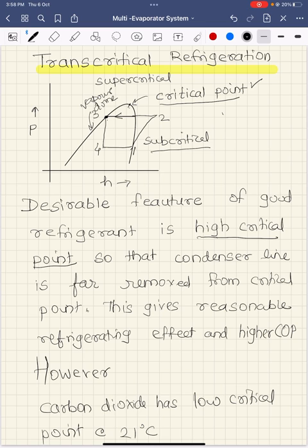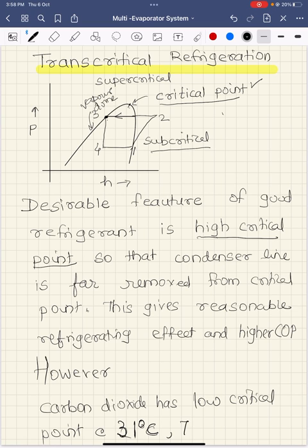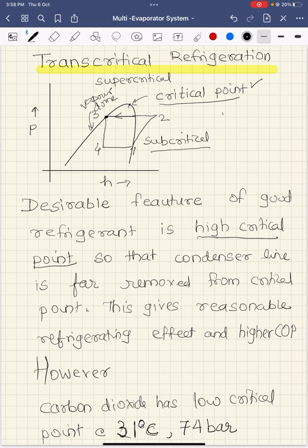What is the transcritical cycle? If you are referring specifically to carbon dioxide, carbon dioxide has a problem in that it is not an ideal refrigerant with respect to the critical point property. The desirable property for a good refrigerant is that the critical point has to be high, but for carbon dioxide the critical point is pretty low — around 31 degrees Celsius. The critical pressure is around 74 bar. The condensation point happens at around 30–35 degrees Celsius, so when ambient temperatures are that high we cannot design a refrigeration system with CO₂ in the subcritical region. For that, we need to look at the transcritical cycle.